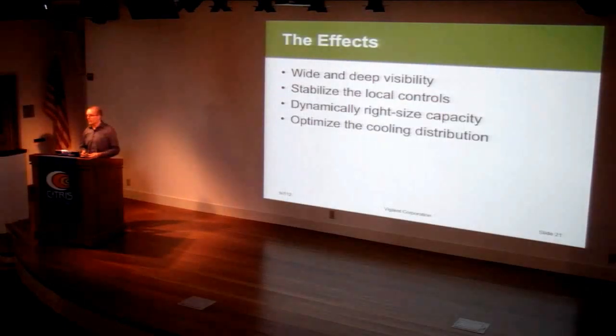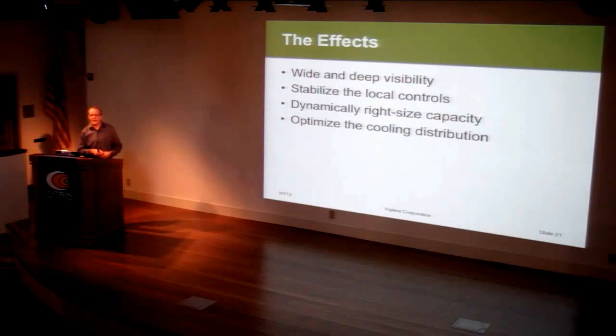The first thing the software does is stabilize those unstable local controls. It dynamically right-sizes all that capacity, figuring out what should be on, what should be off, what should be turned up or down in a gross way, and then it optimizes the distribution. So maybe you don't need so much cooling over there and you need more over here. It figures that out and optimizes it in a way that uses the least amount of power.